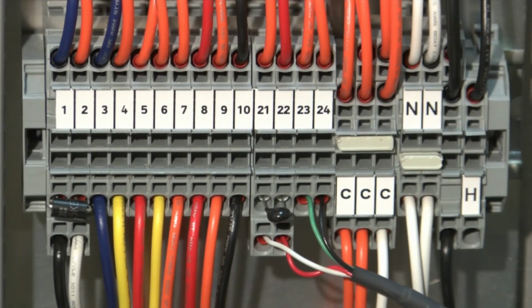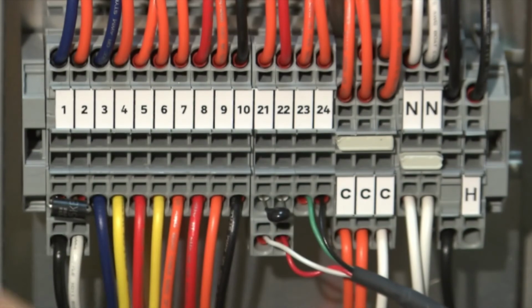The MistFree system also utilizes two surge arresters in conjunction with its fuses. There is a surge arrestor for the 48 volts located across terminals 1 and 2, and there's a surge arrestor for the 24 volts located across terminals 21 and 22. A surge arrestor protects the circuit in the event of a power surge. If too much voltage comes through the circuit, the surge arrestor will arrest and create a short, blowing the corresponding fuse. If you have a blown fuse that you replace with a new fuse, and this new fuse immediately blows, you're going to want to check your surge arresters, as that is likely the culprit.